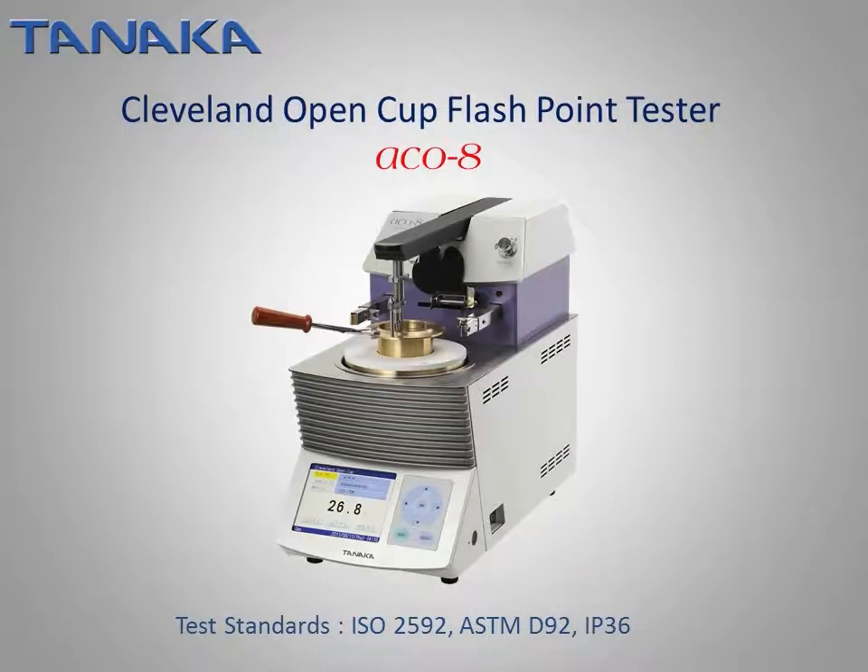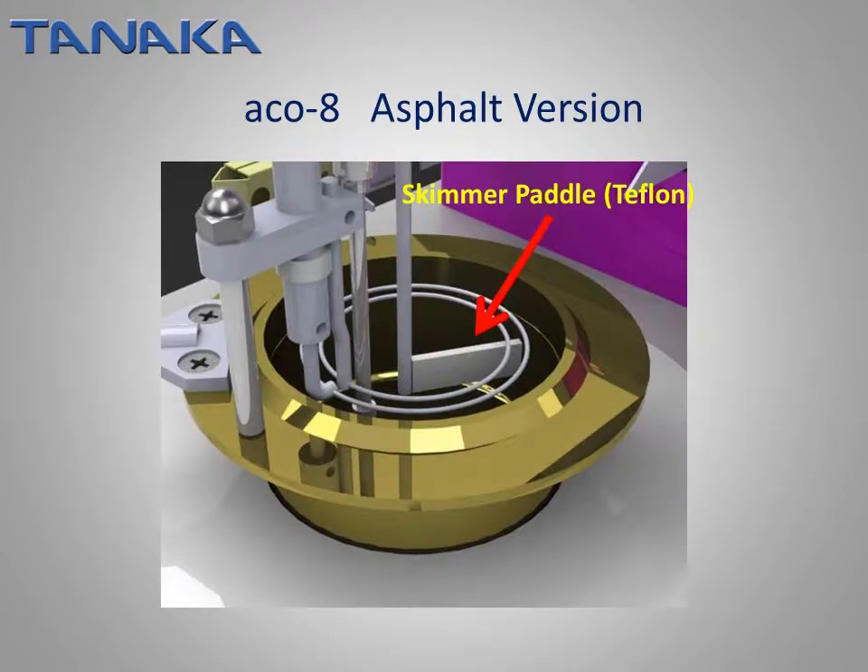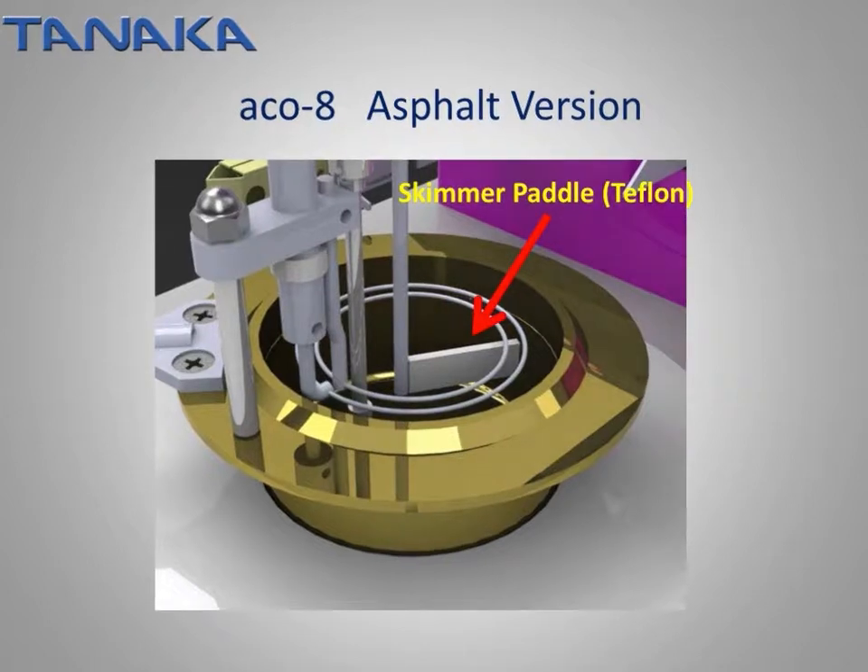The Cleveland Open Cup Flashpoint Tester, model ACO-8, conforms to ISO 2592, ASTM-D92, and IP36. Measuring range is room temperature to 400°C. In addition to the flashpoint, firepoint can be determined automatically. The ACO-8 is equipped with a fire containment lid, which activates automatically to help put out fire when the ACO-8 detects a fire point or a specimen catches fire inadvertently. In addition, an ACO-8 with surface skin remover for asphalt is available as the ACO-8 asphalt version.